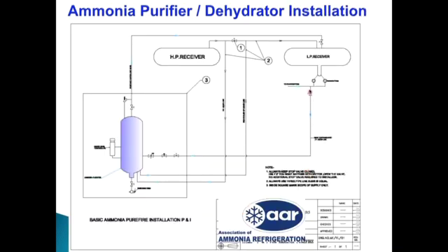In a typical installation, you can see here the liquid is fed from the pump outlet, and this is a high pressure liquid from the receiver going into the system and taken back to the LP vessel. So the heat of this HP receiver, which may be 37, 38 degrees, is used to boil the ammonia.